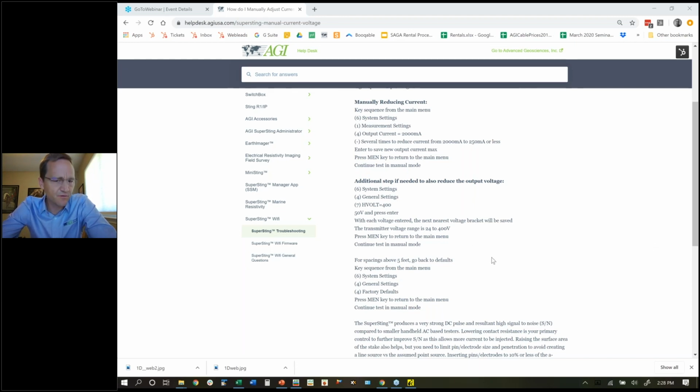SuperStings have a calibration interval of 1 year, and we have NIST traceable capabilities at AGI. And we do have free loaners for owners of SuperStings now. So they can send one out if you're shipping yours in at no cost if you cover the shipping.